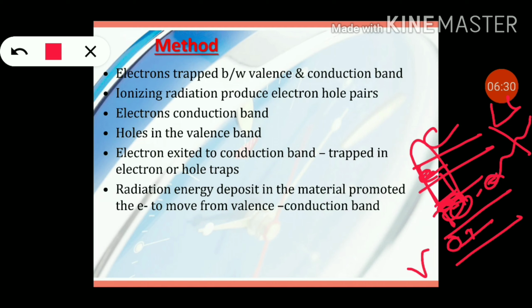Not all the electrons are free from the traps. If the light output from an OSL dosimeter is analyzed over a short period of time, many electrons will remain trapped inside these hole traps. This means the OSLD can be reread many times without significant loss of signal.